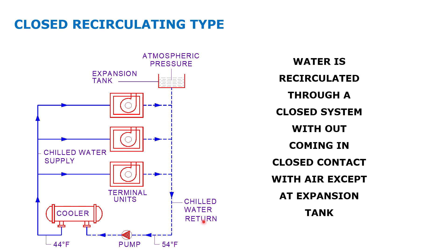In a closed loop system, specifically for the chilled water line, a pump circulates water through the chiller. High-temperature water is cooled down to 44°F (7°C) and pumped to the terminal unit or air handling unit. The same water returns and is recirculated — this is called a closed loop recirculating system.